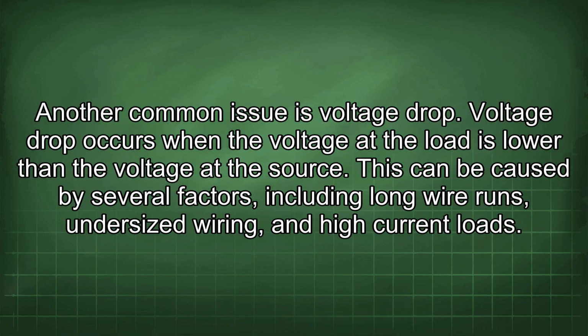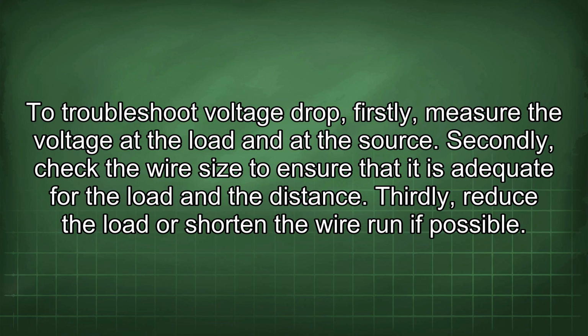Another common issue is voltage drop. Voltage drop occurs when the voltage at the load is lower than the voltage at the source. This can be caused by several factors, including long wire runs, undersized wiring, and high current loads. To troubleshoot voltage drop, firstly, measure the voltage at the load and at the source. Secondly, check the wire size to ensure that it is adequate for the load and the distance. Thirdly, reduce the load or shorten the wire run if possible.